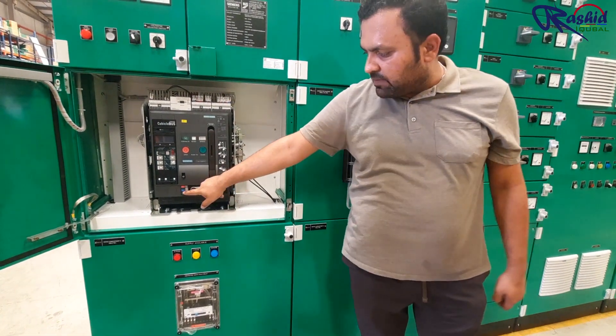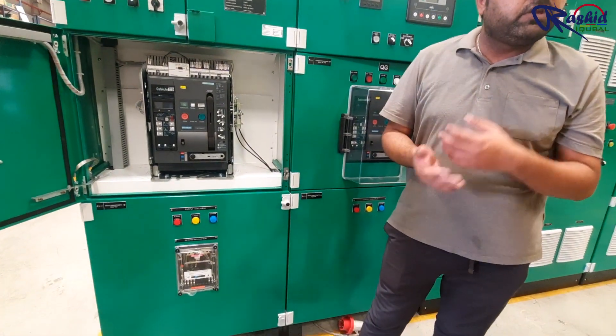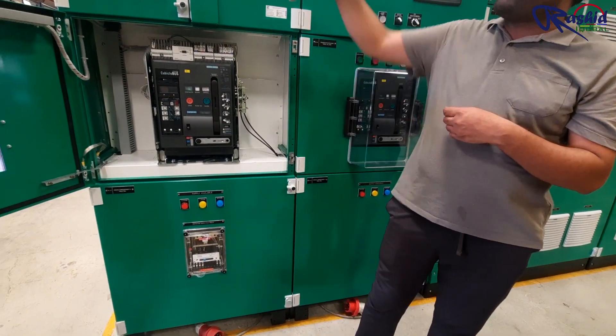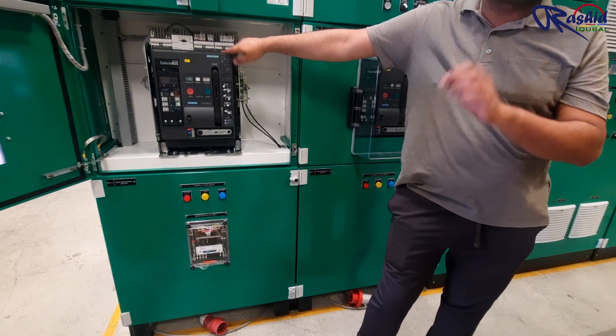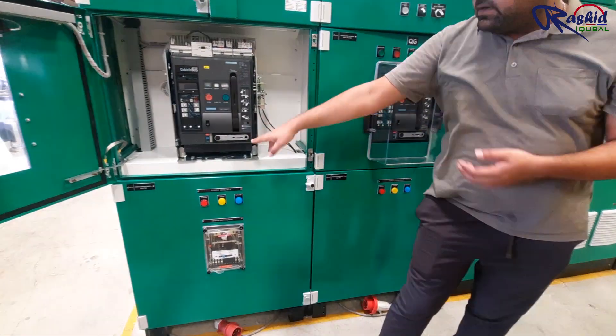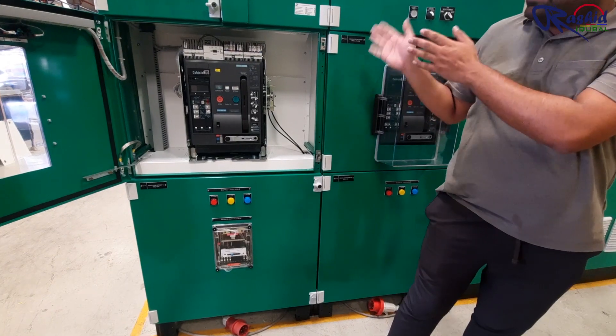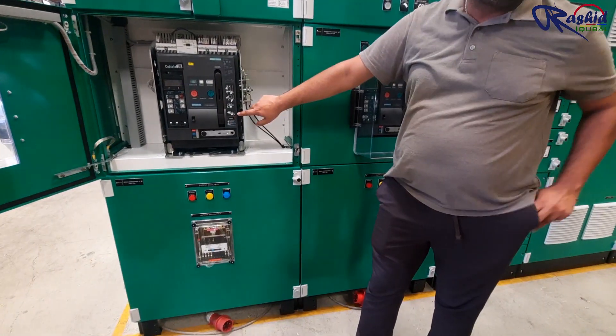The purpose and benefit of the test position is that in case you did some maintenance and you want to be sure but you don't want power to flow in the panel, you can keep the ACB in test mode and verify the operation — like on/off operation only. Disconnect means putting the breakers isolated.